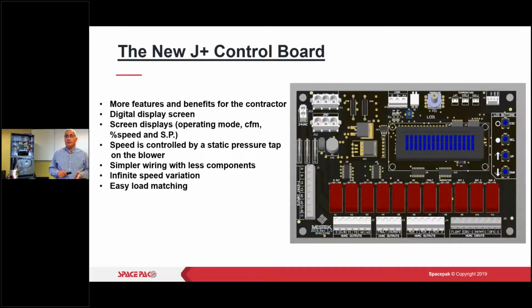So we have a digital display. So that'll give you our operating mode. It'll tell you the CFM, percentage of speed, and your static pressure. We control the speed of the blower by the static pressure tap on the blower, as you can see. Much easier wiring, there's less components. All right, it's an ECM motor, so it's easy to balance out the system now. We're pretty far away from the days where we had to add extra outlets and dump into an attic or dump into a hallway to balance the system. We can do it now at the blower.